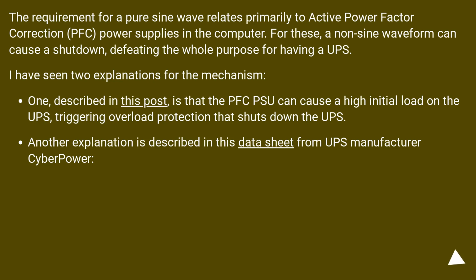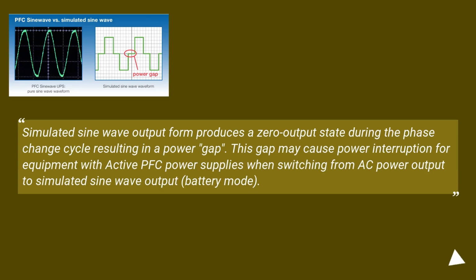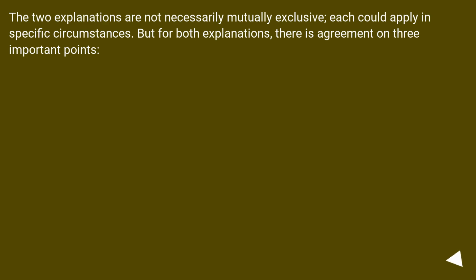Another explanation is described in this data sheet from UPS manufacturer CyberPower. Simulated sine wave output form produces a zero output state during the phase change cycle resulting in a power gap. This gap may cause power interruption for equipment with active PFC power supplies when switching from AC power output to simulated sine wave output, battery mode. The 2 explanations are not necessarily mutually exclusive. Each could apply in specific circumstances, but for both explanations, there is agreement on 3 important points.